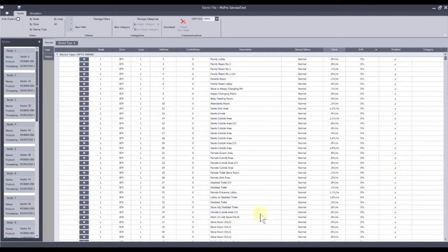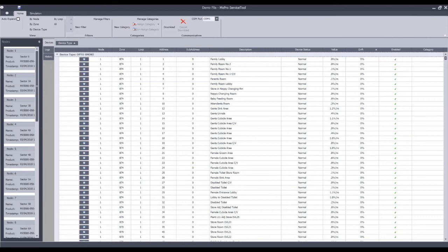The value column: in this example we are using Hochiki devices, which use a percentage of parts per million contamination to reflect the status of the devices. 0% is good, i.e. there is no contamination in the chamber. As we look down the list, we can see a couple of devices that stand out as being slightly of concern: 1.2% and 1.1%, and 1.1% again further down. Hochiki devices will enter a pre-alarm condition if that value reaches 2.5%.